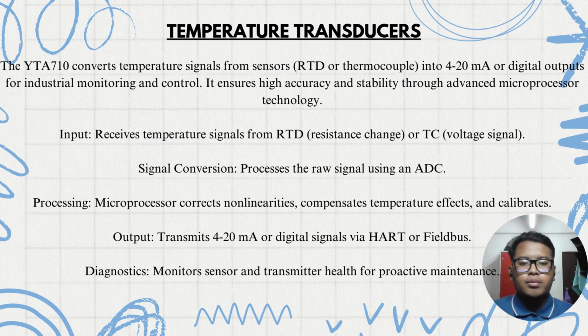It converts the temperature signal from an RTD or thermocouple sensor into 4 to 20 mA or digital output for industrial monitoring and control. It ensures high accuracy and stability through advanced microprocessor technology. Input: it receives a temperature signal from an RTD, resistance change, or a TC voltage signal. Signal conversion: process the raw signal using ADC processing. The microprocessor corrects non-linearity, compensates temperature effect, and calibrates. Output: transmit 4 to 20 mA or digital signal via HART or fieldbus. Diagnostic: monitor sensor and transmitter health for proactive maintenance.